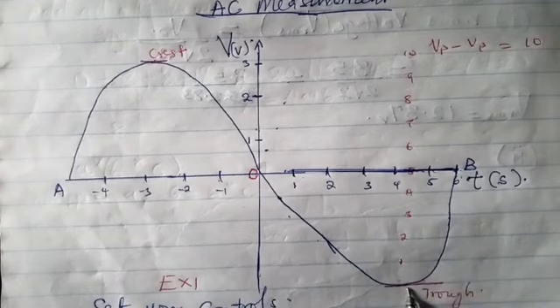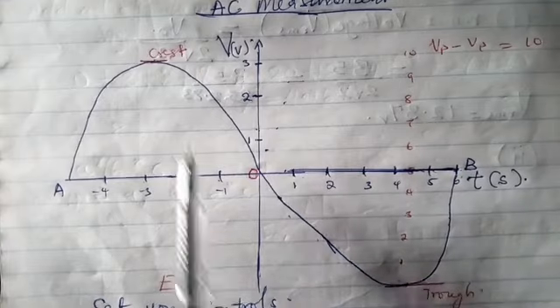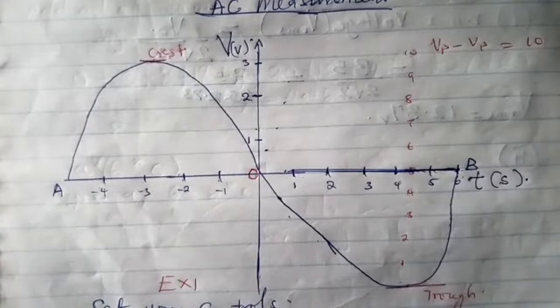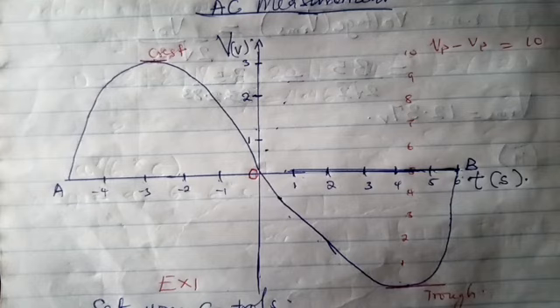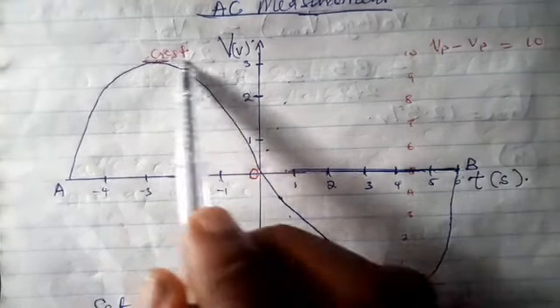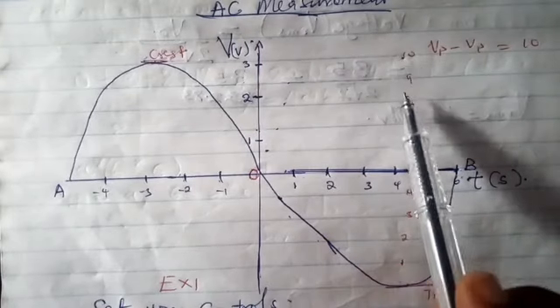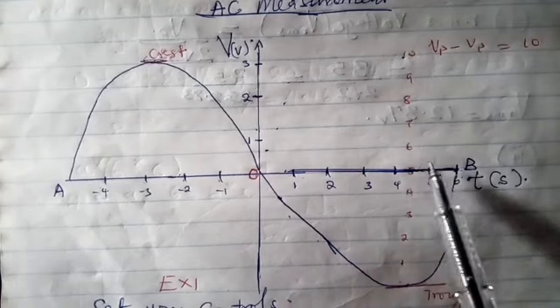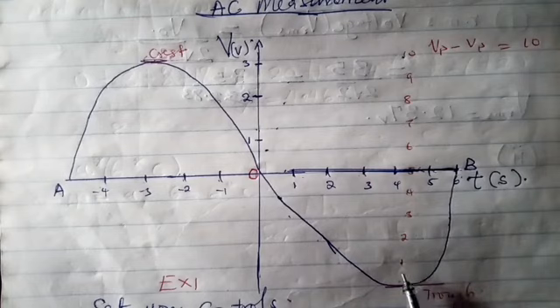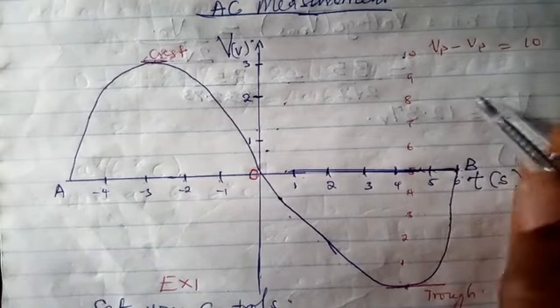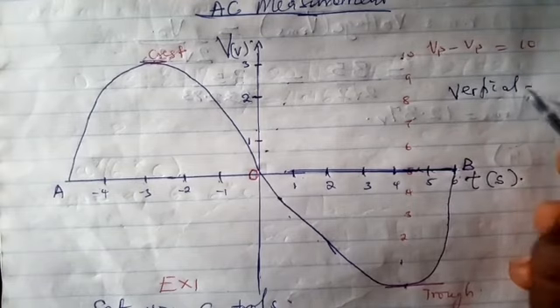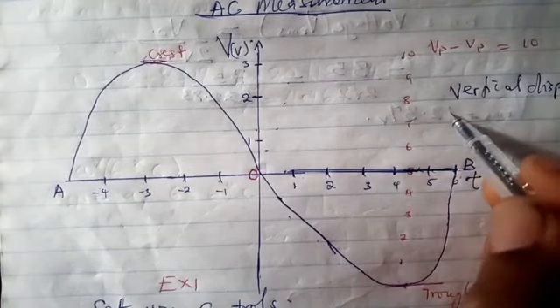If you count from the minimum to the maximum, you have to get the number of divisions. According to some questions, that is what they call vertical display on the screen. Let's count from this place. We have 0, 1, 2, 3, 4, 5, 6, 7, 8, 9, 10. So we can have a vertical display of 10.